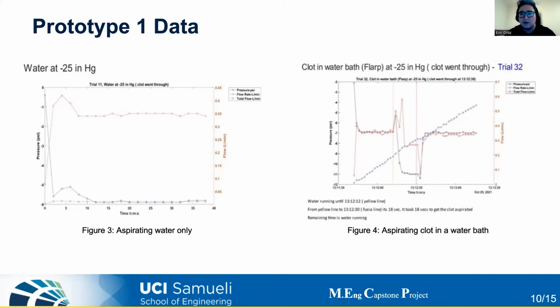On the right, we have a little bit more detailed data of what's going on during a clot aspiration. Going from left to right, we have that water was flowing through the system, the catheter came into contact with the clot, then got aspirated, and then eventually went through the catheter system and returned back to normal. As you can see, the time frame, it took many seconds to go through the system and not enough fidelity to really be an accurate model.